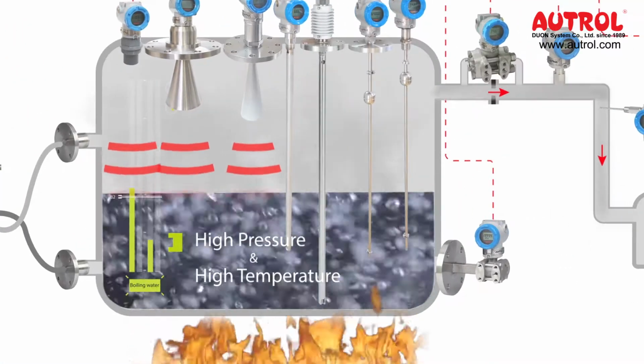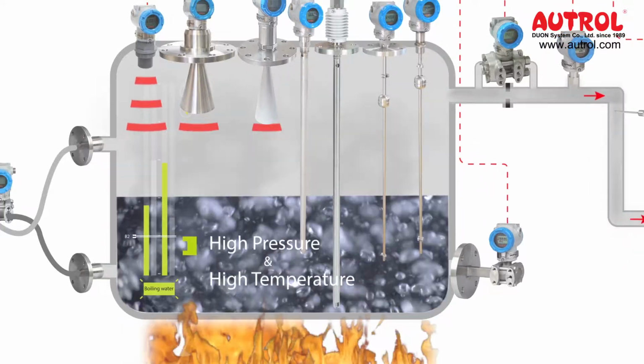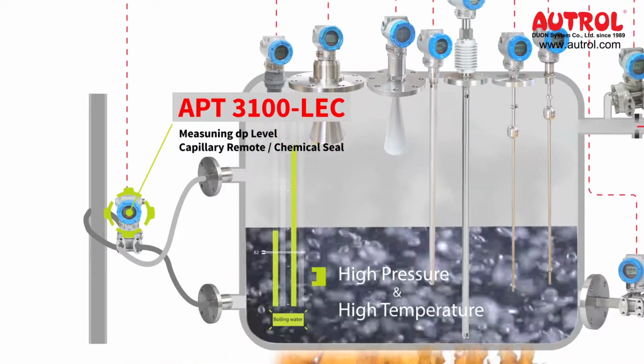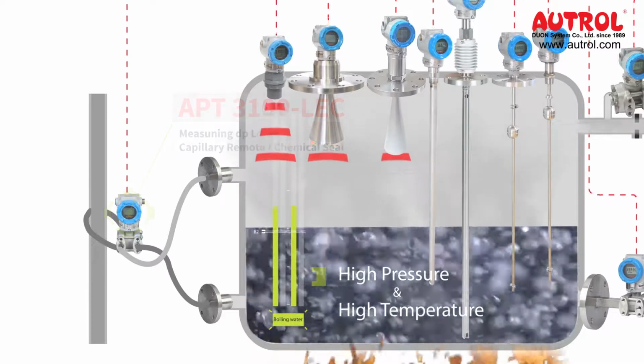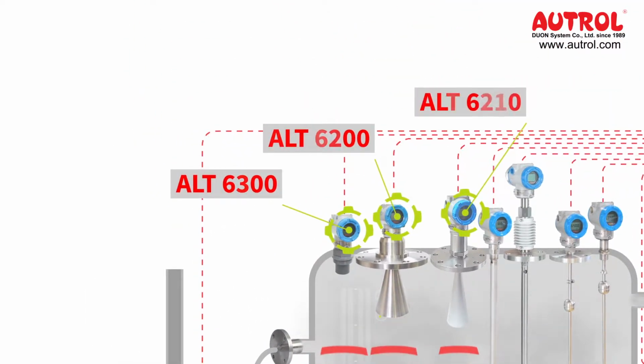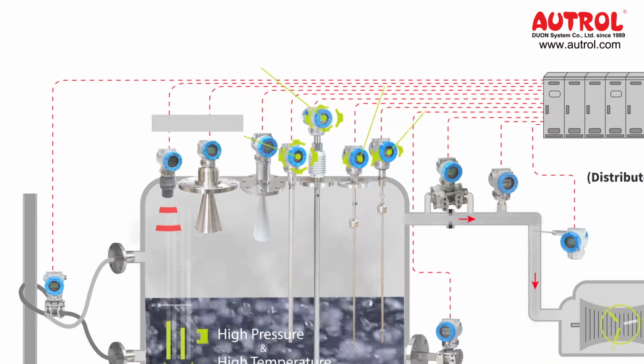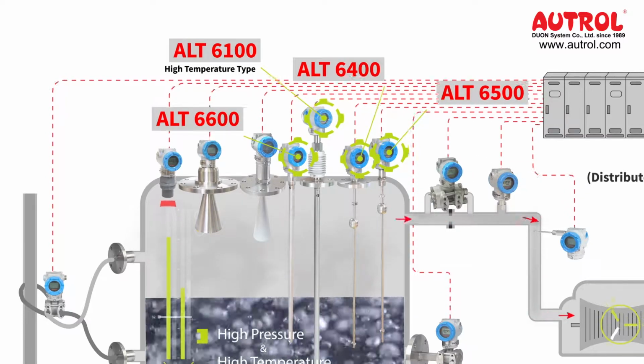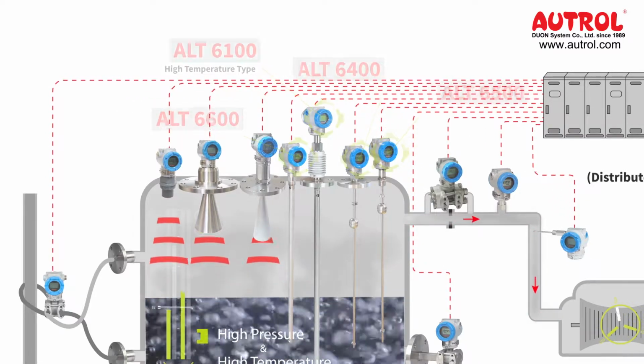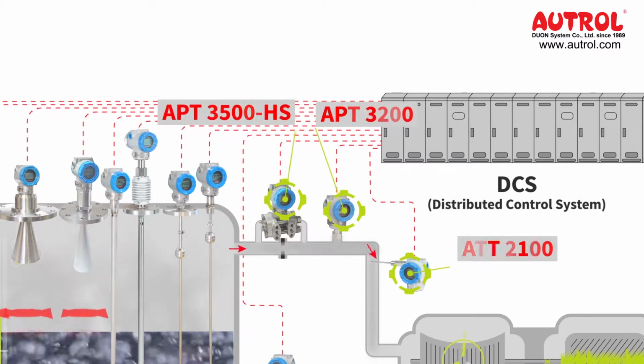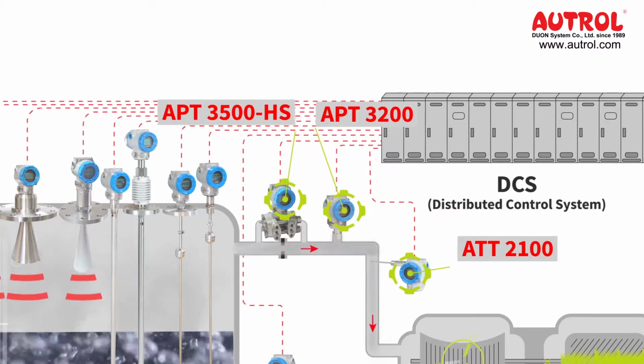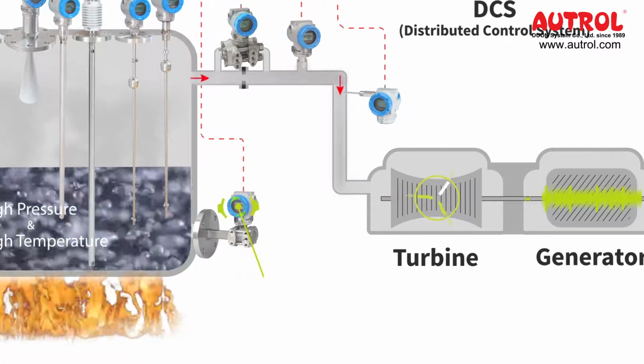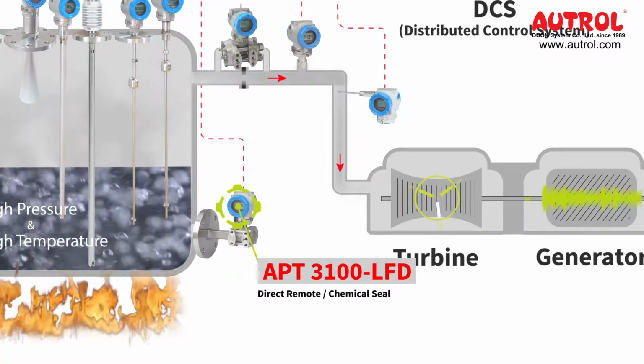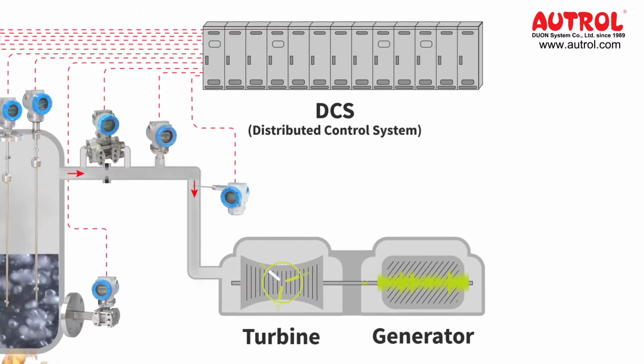The smart transmitter takes a central role in facility efficiency and risk management in the process line. In a thermal power plant, for example, there is a fuel-fired boiler for power generation, heating the boiler to a high temperature to generate steam. In this case, each pipeline is managed by measuring its pressure, temperature, and level. The AUTROL Smart Transmitter measures those physical values and transmits them to a remote control system, such as DCS and PLC, with an analog signal of 4 to 20 milliamperes and the digital HART protocol. Therefore, each process line is enabled for remote supervisory control.